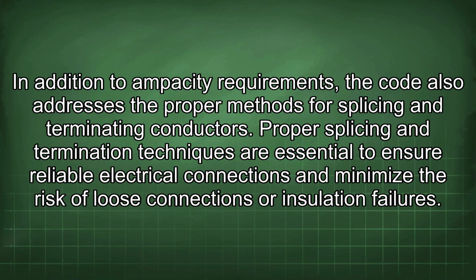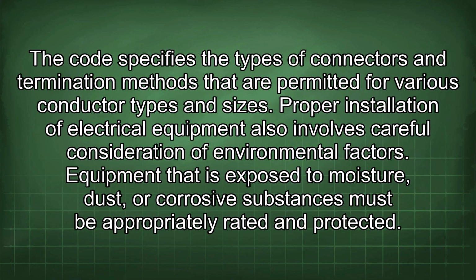In addition to ampacity requirements, the code also addresses the proper methods for splicing and terminating conductors. Proper splicing and termination techniques are essential to ensure reliable electrical connections and minimize the risk of loose connections or insulation failures. The code specifies the types of connectors and termination methods that are permitted for various conductor types and sizes.